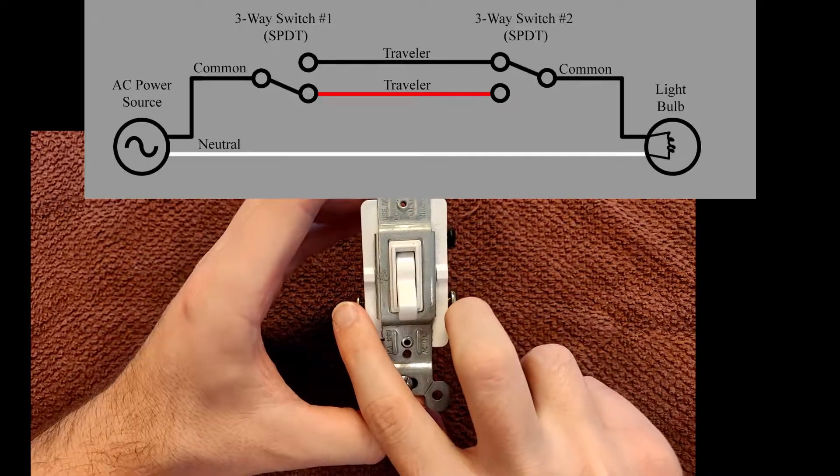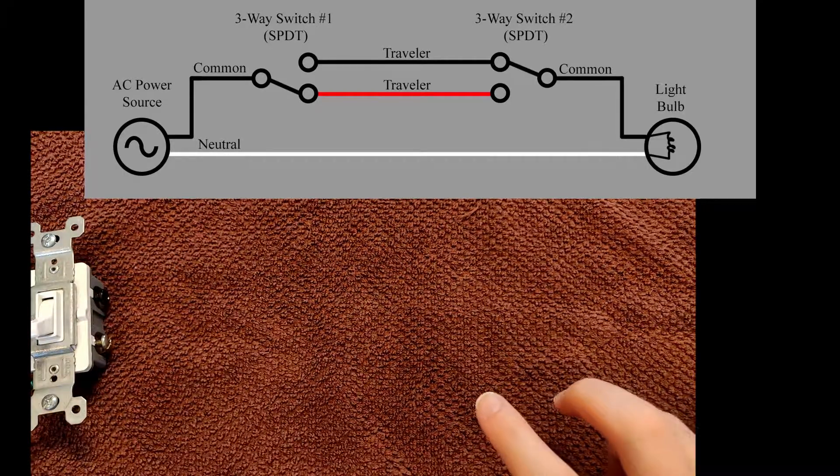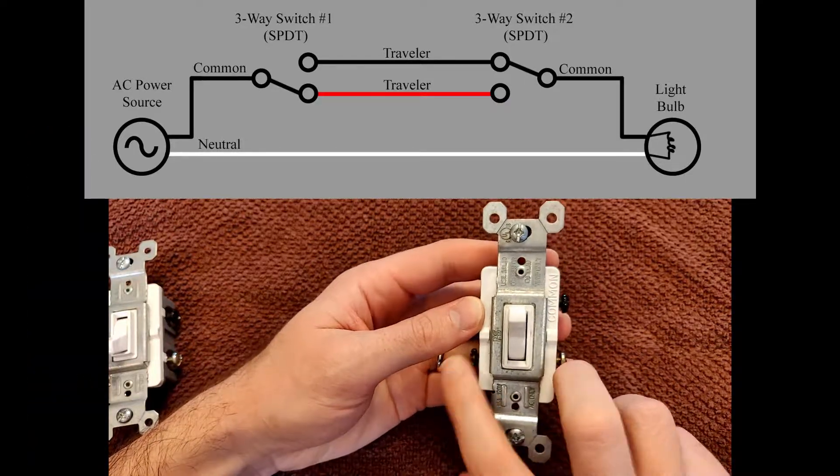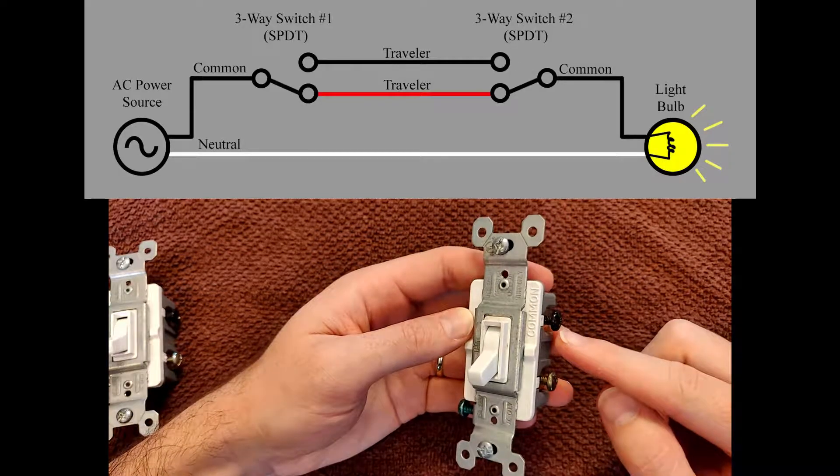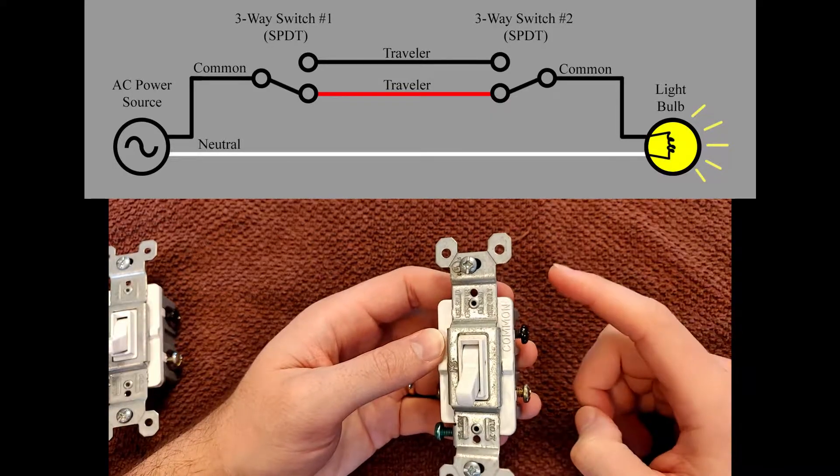This will then travel from this switch through the wires in the wall over to a second three-way switch. Those two hots will come onto this switch. Then depending on which way this switch is flipped, it will send this common screw power, and then the power gets from this common screw over to your light fixture.